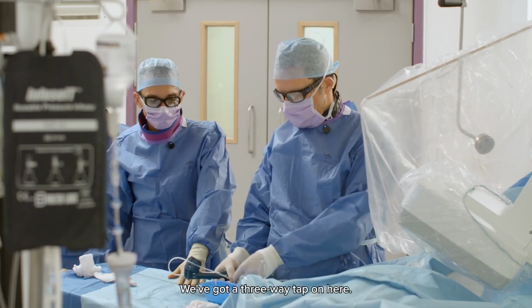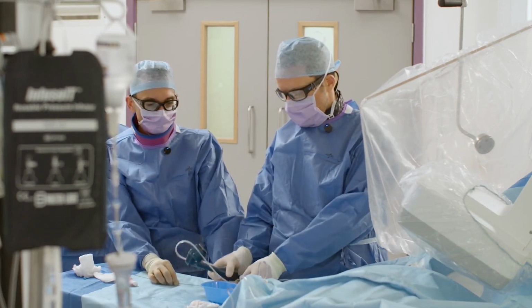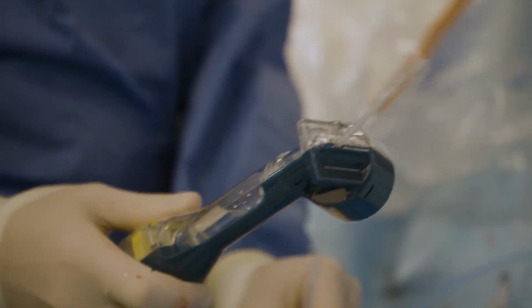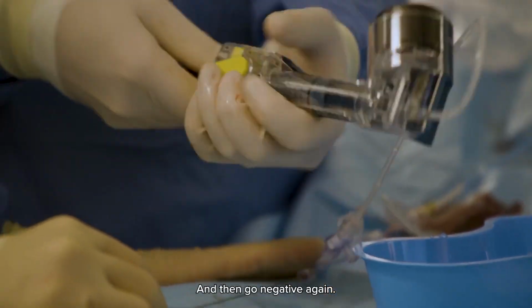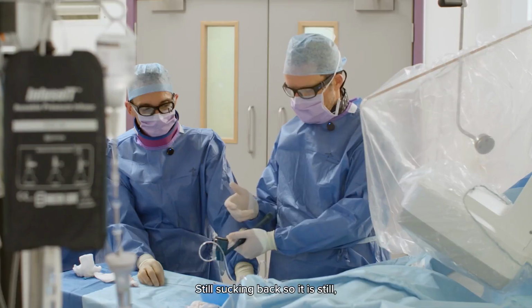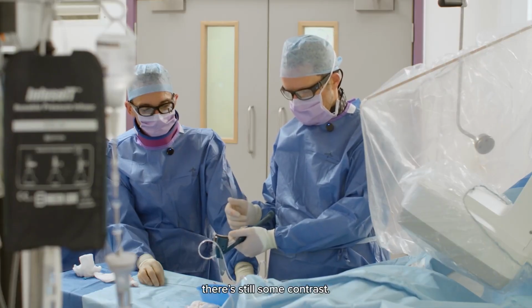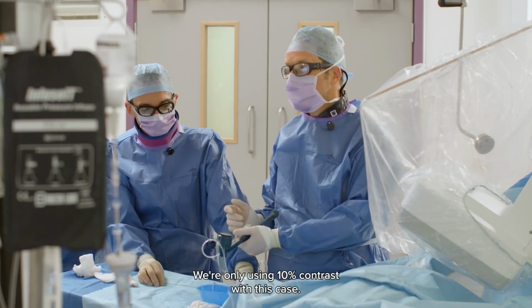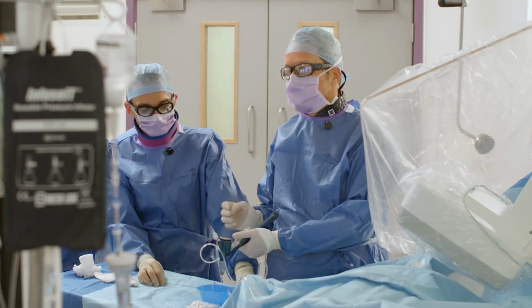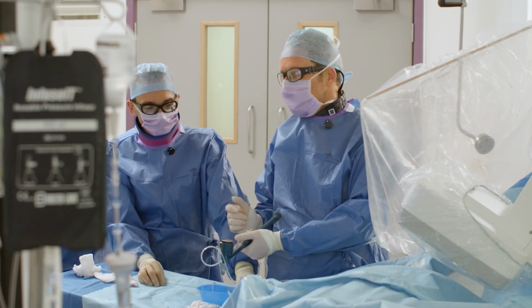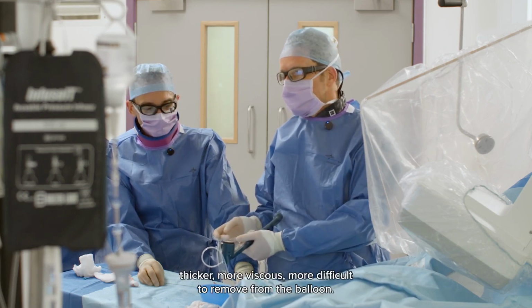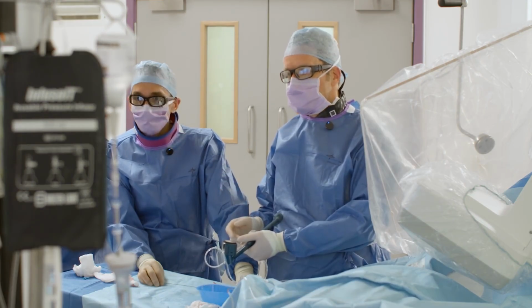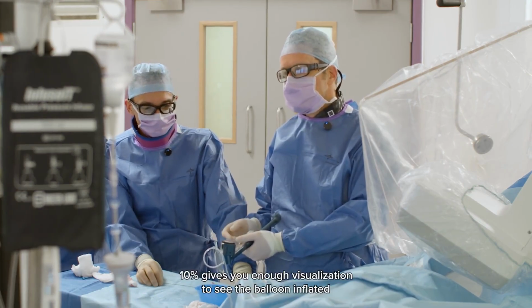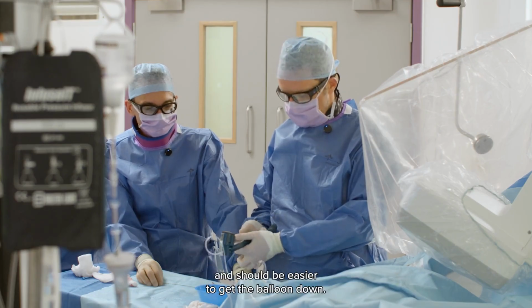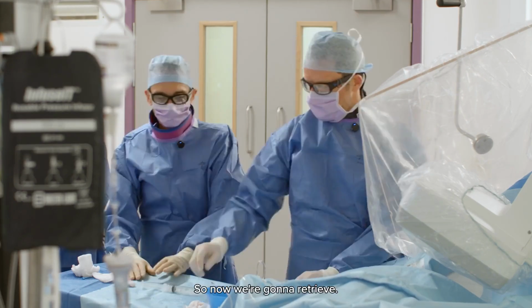We've got a three-way tap on here. We're going to close it to the balloon, empty the contents, and then go negative again. Still sucking back, so there's still some contrast. We're only using 10% contrast for this case. 20% is obviously thicker, more viscous, more difficult to remove from the balloon. So 10% gives you plenty, 10% gives you enough visualization to see the balloon inflated and should be easier to get the balloon down. So now we're going to retrieve.